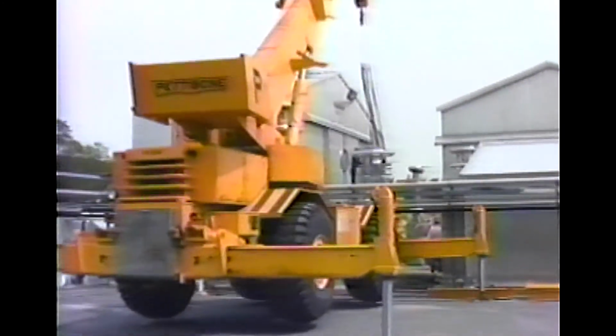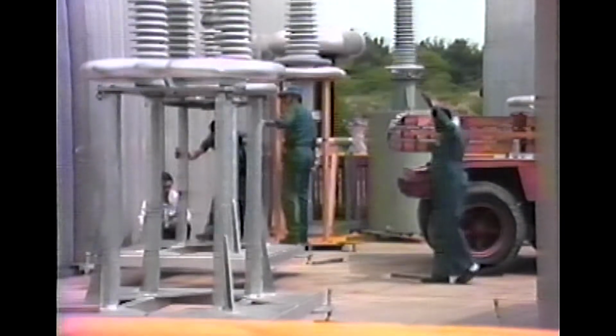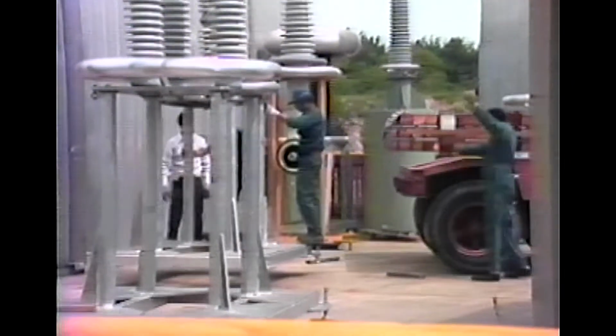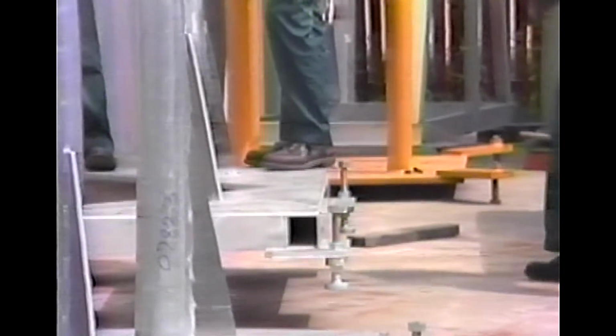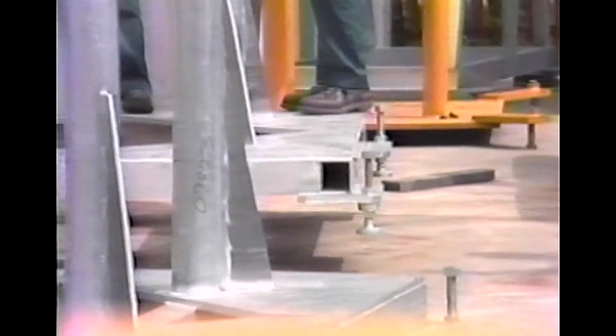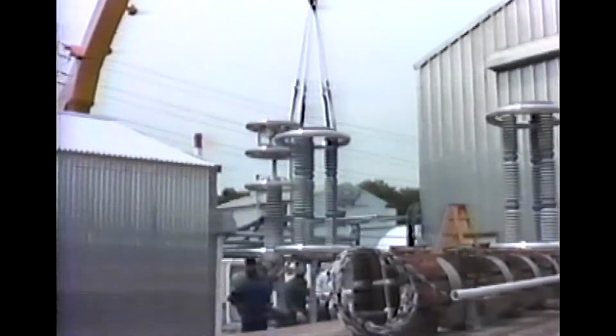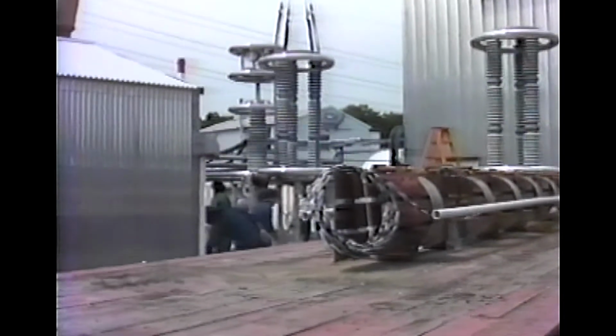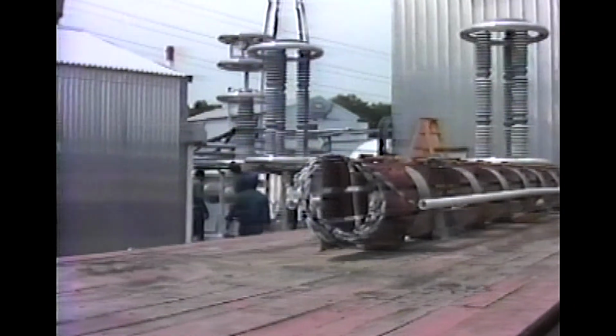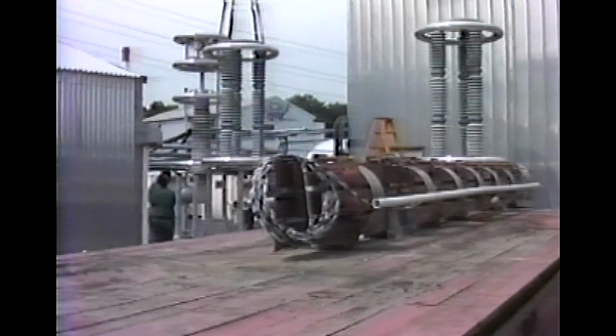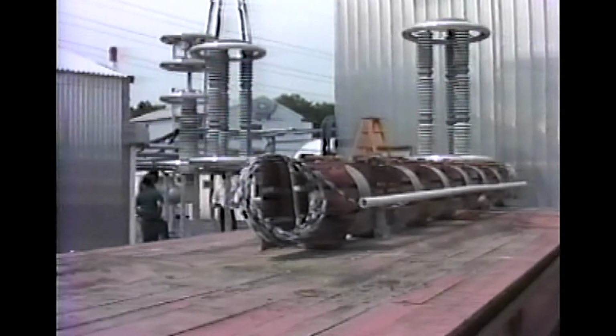As the termination assemblies neared completion, work started on the electrical bus bars which connect the terminations to the supply equipment. The power supplies provide simultaneous voltage and current at the correct level to energize the cables to the maximum rating of the system. Although the cables will carry a great deal of power, it is not actually used or turned into heat. Power is simply transmitted on a round trip to one end of the cable enclosure and back, and then returned to the electrical supply network feeding Brookhaven Laboratory.